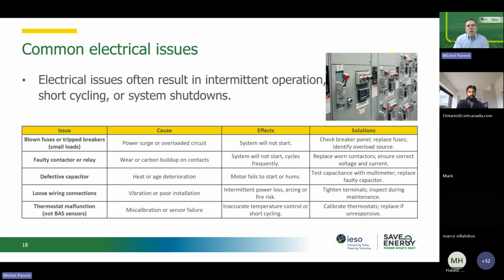So if you've got small loads, obviously you could just have a breaker that flips, so you have to go back and reset the breaker, which can be done by your in-house staff without calling an electrician. But if it trips all the time, then you have a bigger problem. Most people will know that: you just don't reset your breaker all the time. If it trips all the time, that breaker actually will go bad also, because it has a limited number of trips that it can sustain. A breaker is not a switch. So you have to identify what the source of that overload is. And then usually that means, again, asking for an electrician to come in.